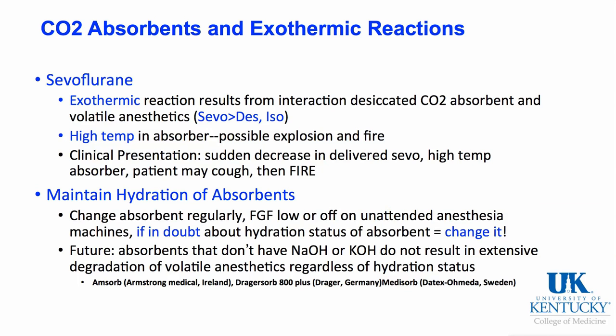Sudden decrease in delivered sevoflurane, a high temperature absorber, the patient may cough because of the heat going into their lungs, and then a fire. Keep the absorbents moist, change them regularly. As I mentioned, if the fresh gas was left on high, if in doubt and you think it's dry, change it out.